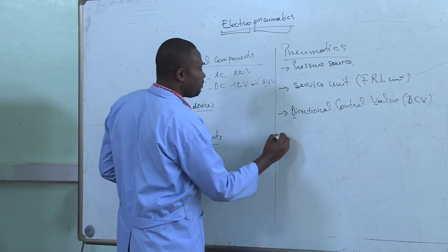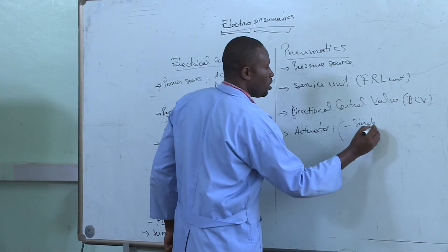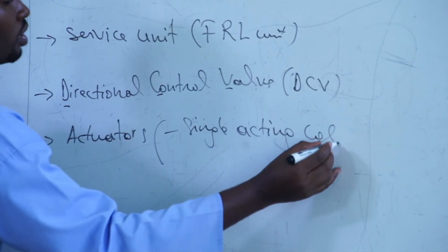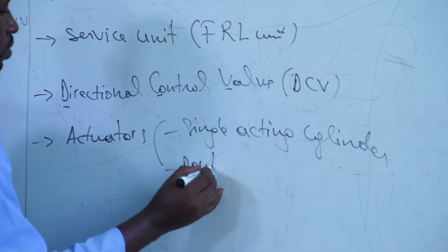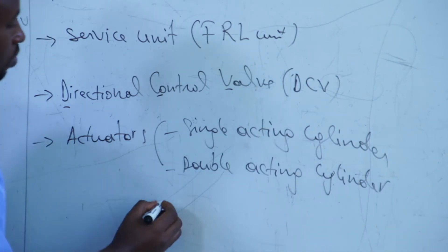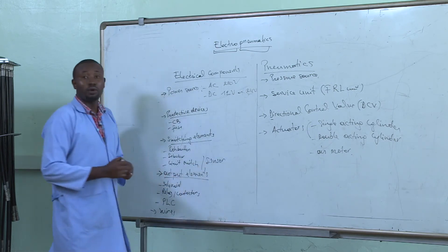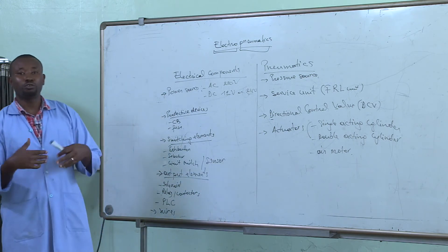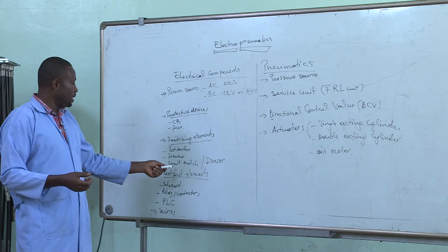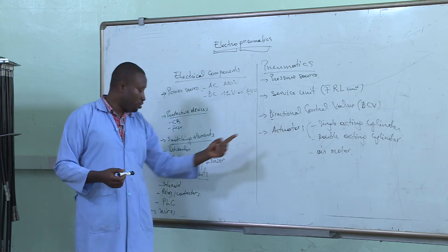We will also need actuators, which can be single-acting cylinders, double-acting cylinders, or even an air motor. Coming back to the electrical system, when you hear 'limit switch' you can also understand 'sensors.' The limit switch or sensors bring feedback information to the control system — that is, the electrical system. They may sense the location of the actuator so that the feedback information comes back to the directional control valve through the solenoid.